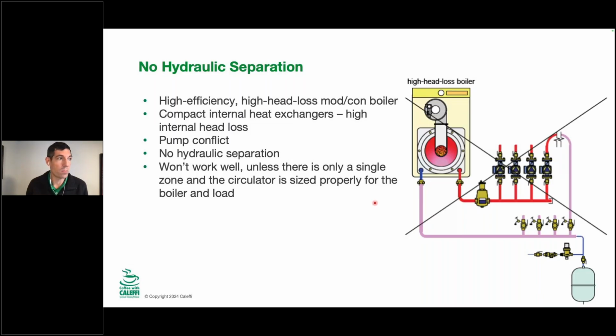This became a bigger issue because what happened in a lot of cases, the reason that we've got kind of the self-explanatory X here, is that in the past, maybe this whole box was a cast iron boiler. And it was pretty flexible to the different flow rates going through that heat exchanger. It was a big buffer capacity of a bunch of cast iron sections that you had a lot of volume in that heat exchanger. So you could have really high flow rates or really low flow rates, and it wasn't going to cause the boiler to run into an overshoot situation or go out on some sort of high temperature limit.